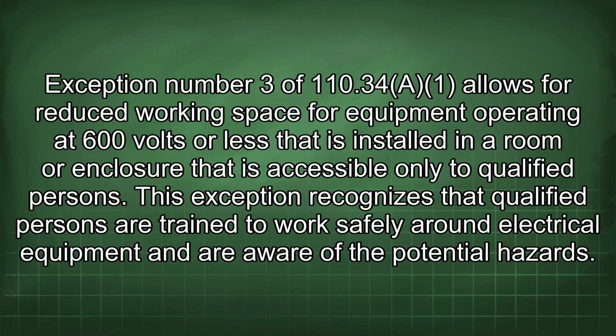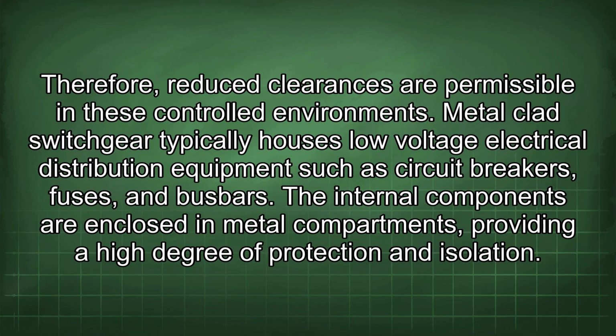Exception number 3 of 110.34(A) allows for reduced working space for equipment operating at 600 volts or less that is installed in a room or enclosure that is accessible only to qualified persons. This exception recognizes that qualified persons are trained to work safely around electrical equipment and are aware of the potential hazard. Therefore, reduced clearances are permissible in these controlled environments.